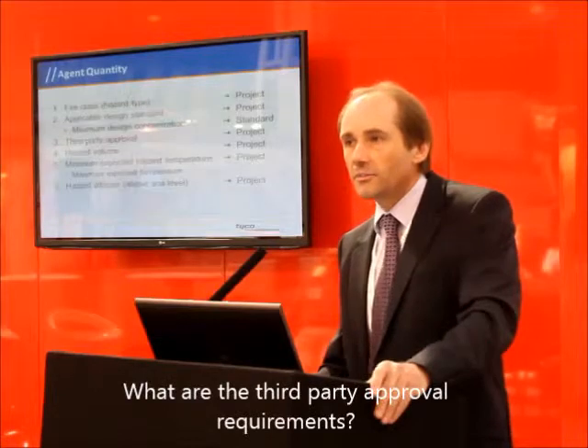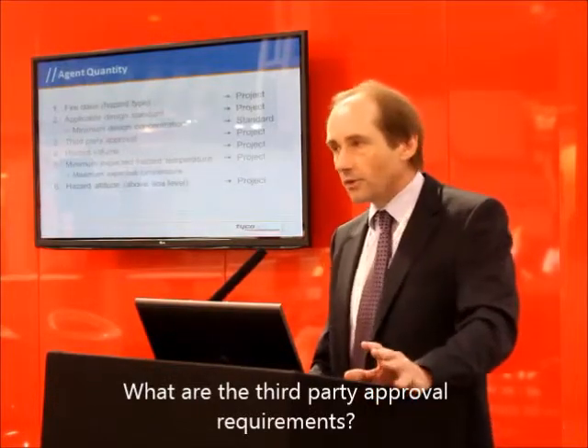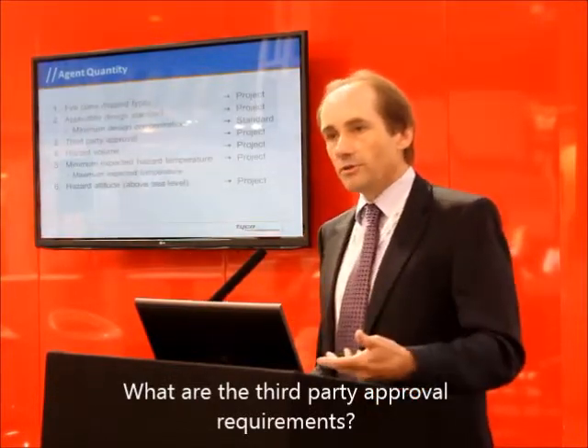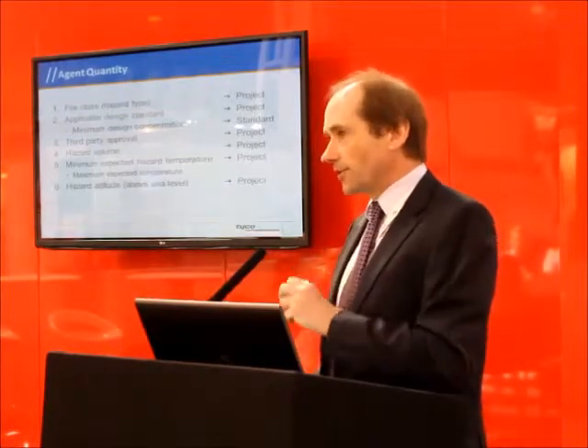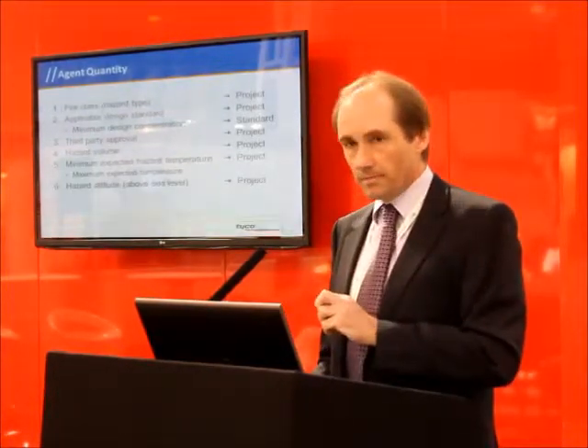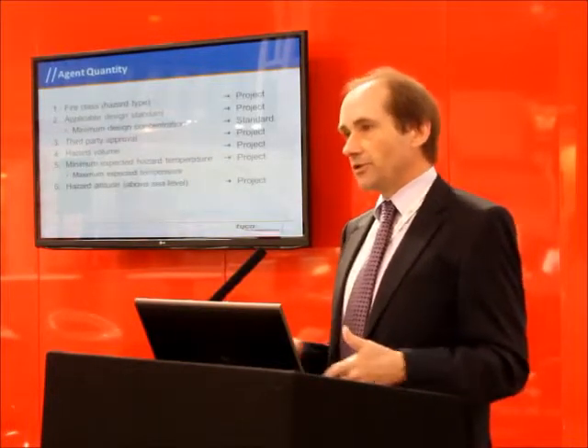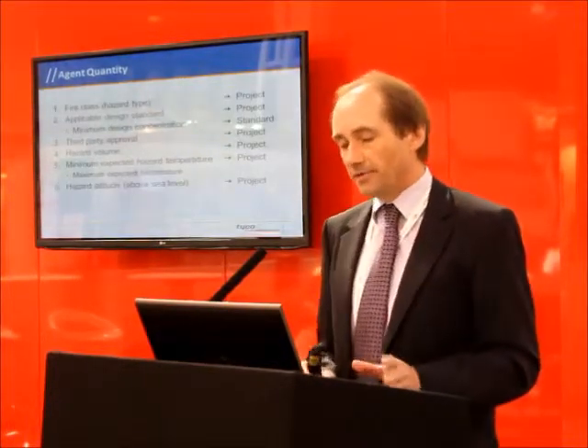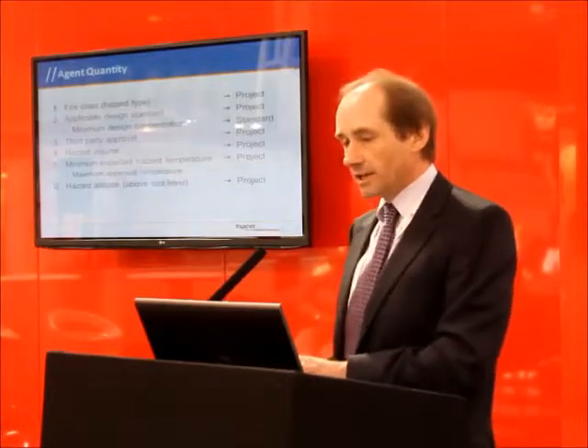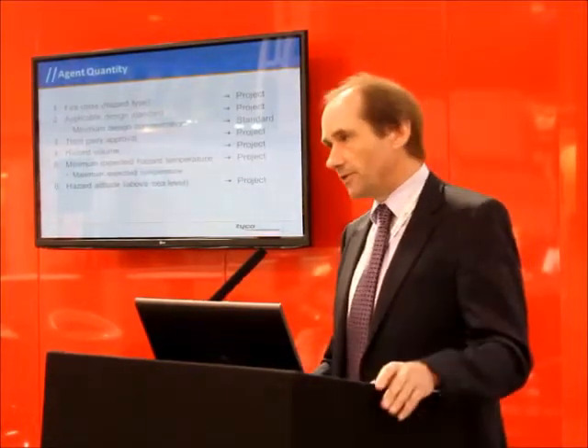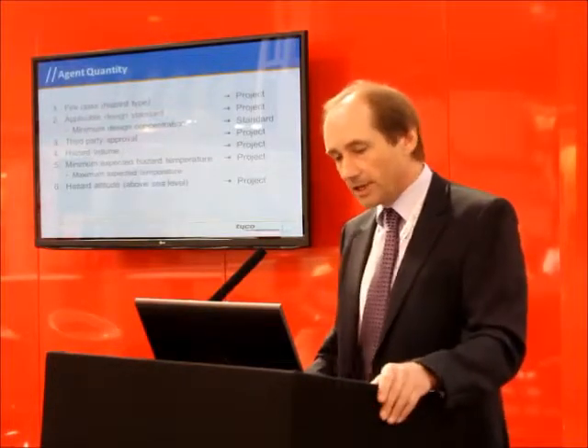What are the third-party approval requirements? All of the agencies have their own rules, requirements, and their own different approval considerations for hardware and equipment. The European market has made it easier, but there is still at times a preference for an LPC system if it's in the UK, or a VDS system if it's in Germany, or a UL system if it's in the Middle East.